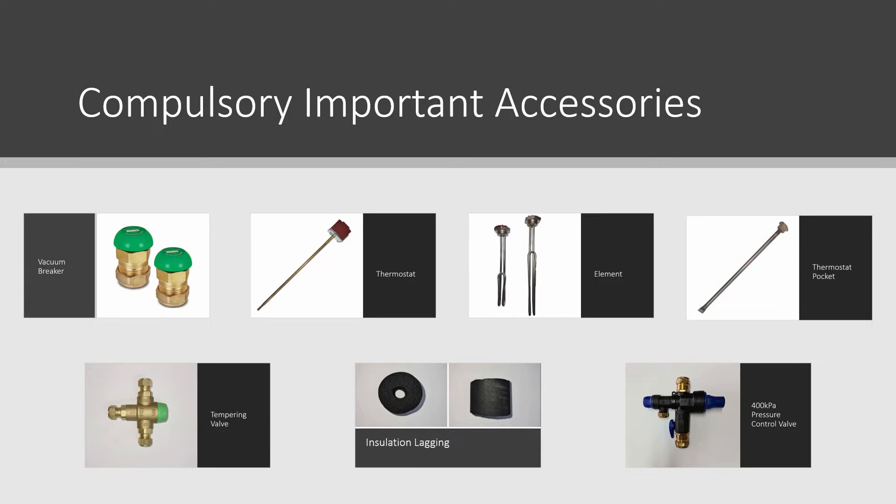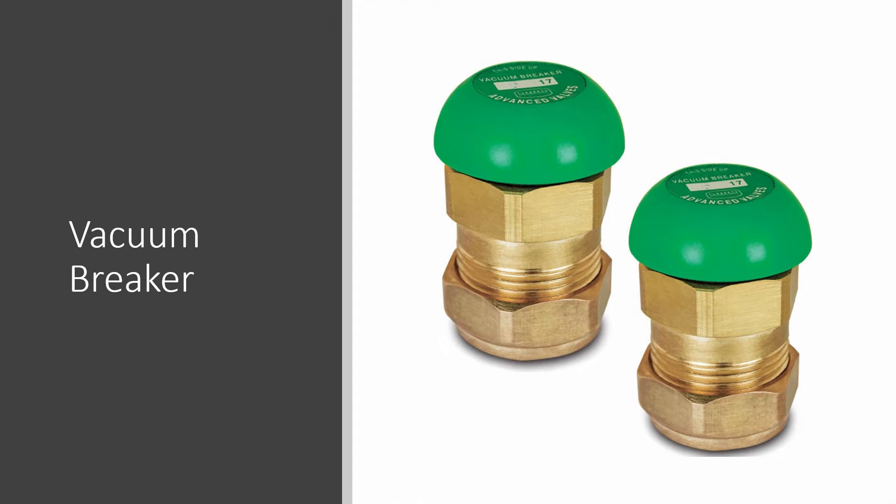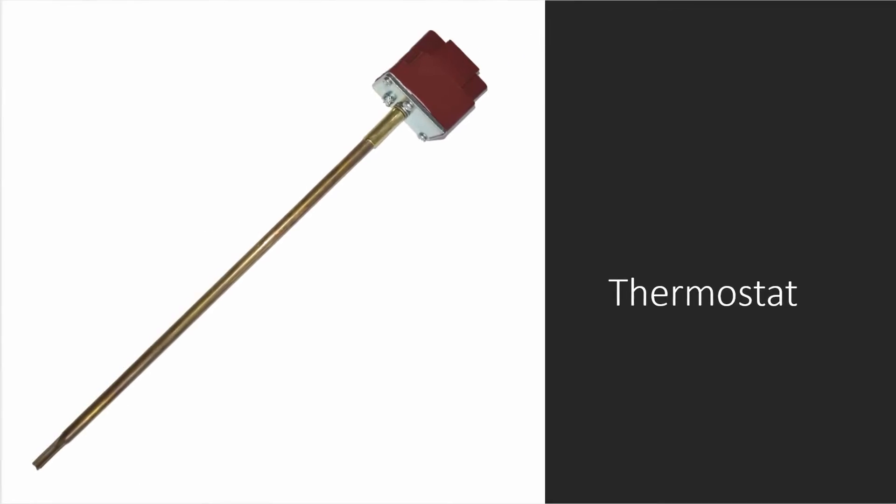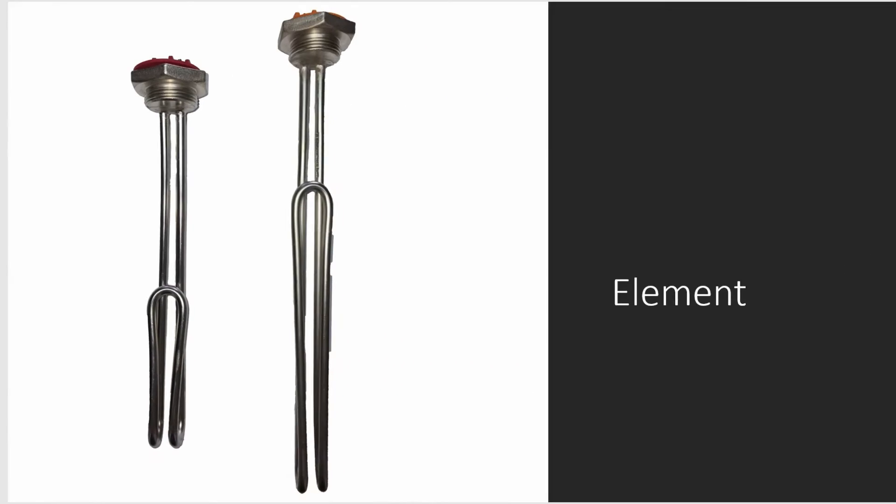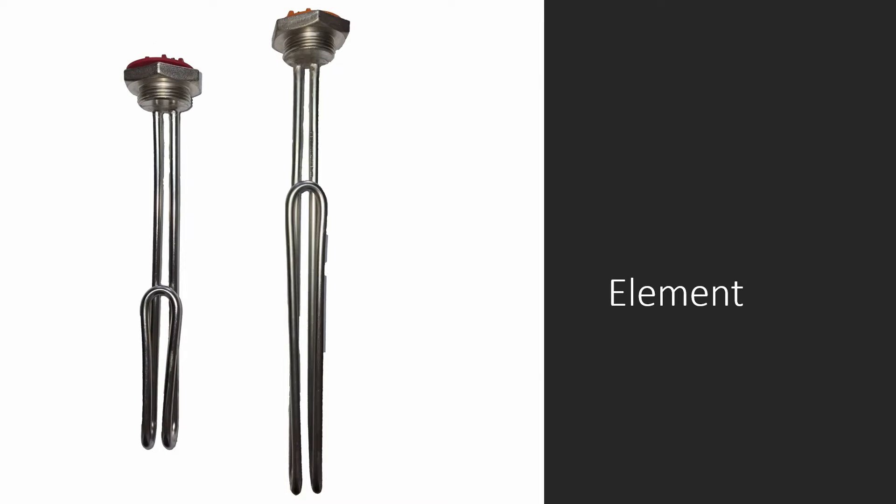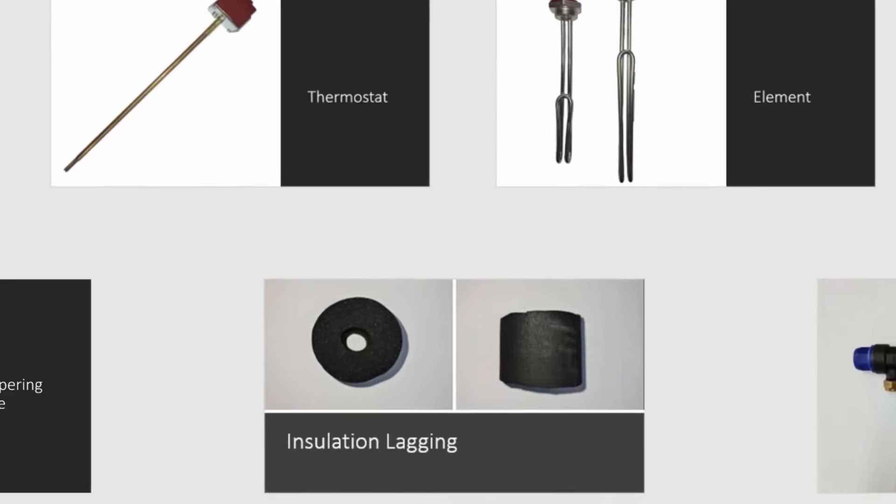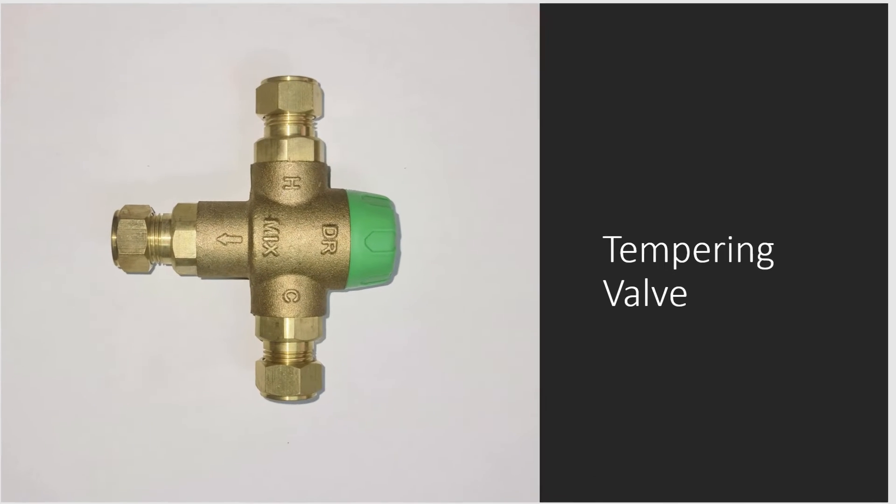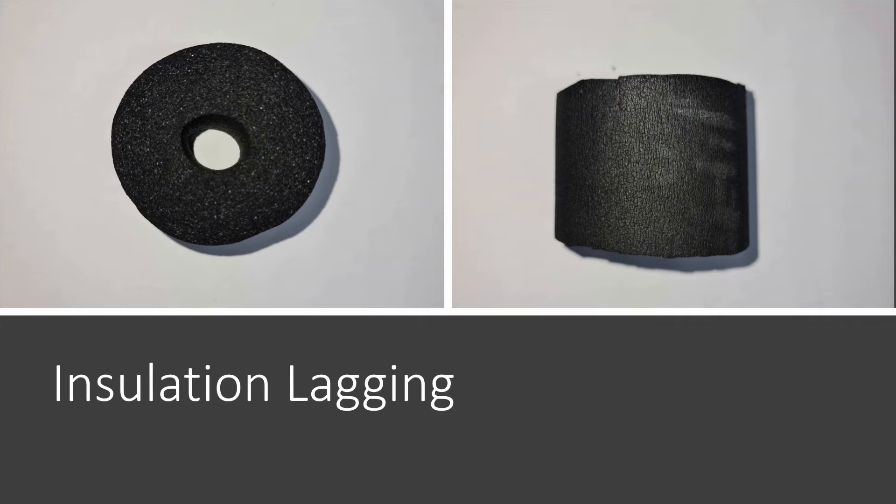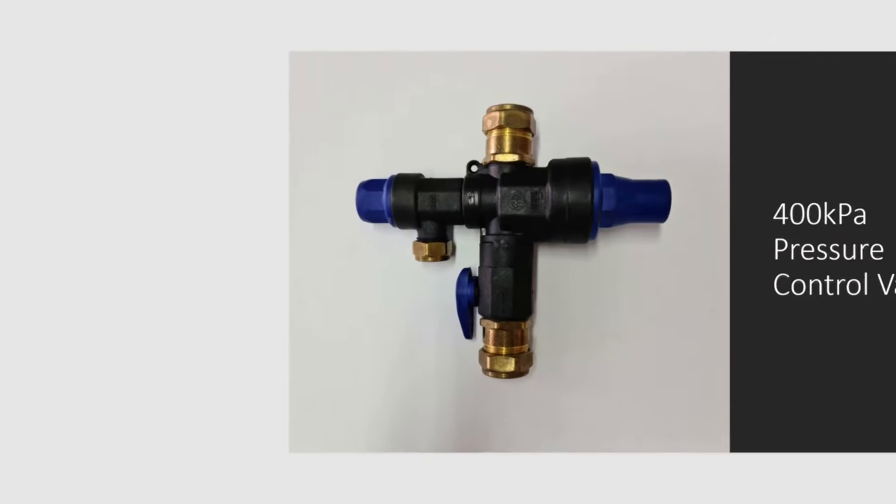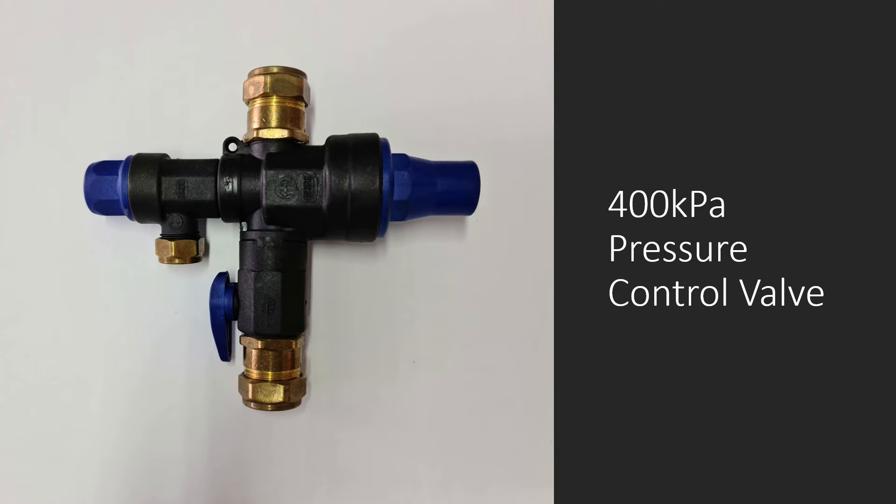Important accessories that are compulsory for installation but not included in the system packing list are vacuum breakers, thermostat, 2kW or 3kW element, thermostat pocket, tempering valve, insulation lagging, and 400kPa pressure control valve. Please note, a pressure control valve or relief valve must be installed along the cold water inlet pipe according to regulations.